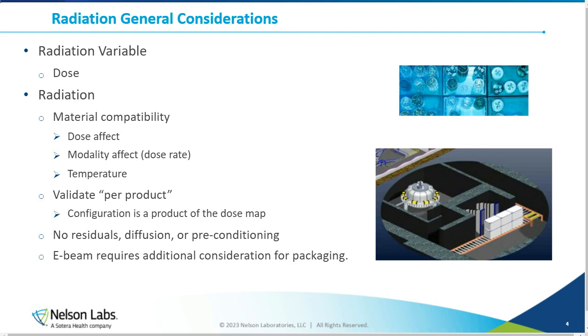The next topic is general considerations for radiation. With radiation, our variable is dose. Temperature, time, gas concentration, all of that goes away, and our variable is dose. One thing we also want to consider with dose is the dose rate, and we'll go over that in a few moments. With radiation, a concern is material compatibility. With ethylene oxide and other modalities, it's either compatible or it's not. I can run it through the chamber or I can't. With steam, it's going to pass or it's going to melt. With radiation, material compatibility is going to be our main concern.